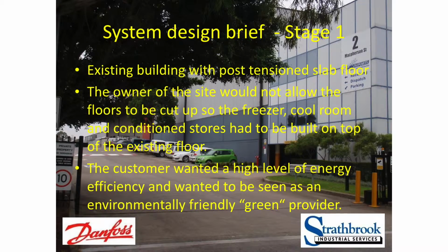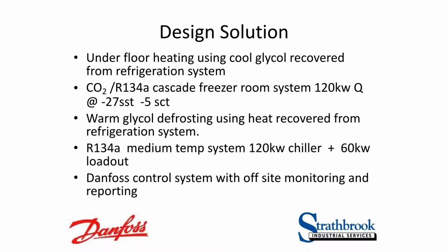So they're over at Botany. They took a lease out on a large site that had a post-tension floor, so we weren't allowed to cut into the floor or anything. It's a freezer room, so they needed subfloor heating, and they wanted basically a green credential and a lower energy bill. So we came up with a glycol underfloor heating system that would be heated by heat recovered from the R134A package. We used warm glycol to do the defrosting of the system, which is also recovered from the discharge of the 134A systems.